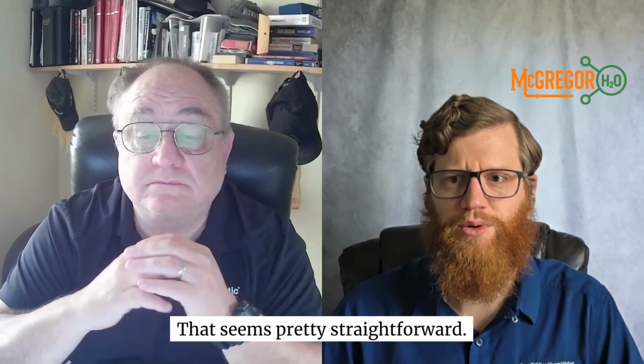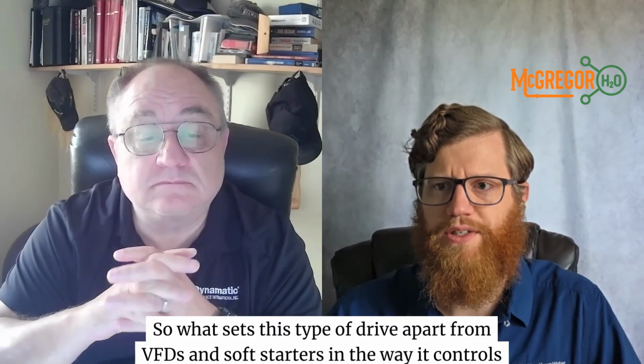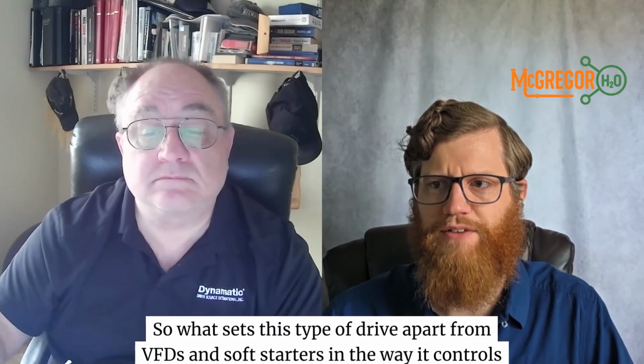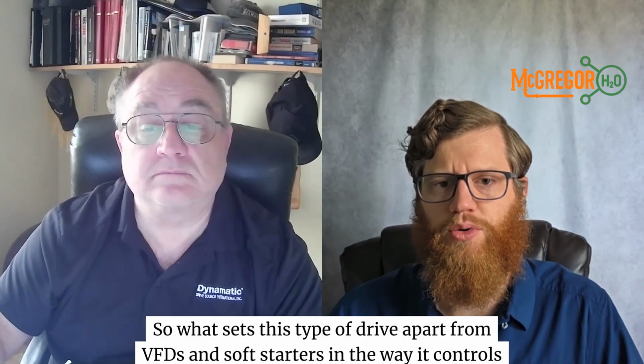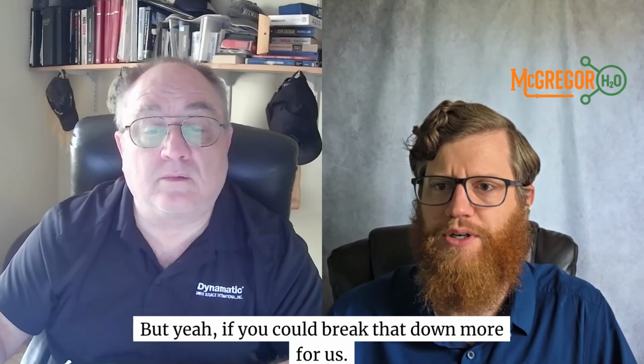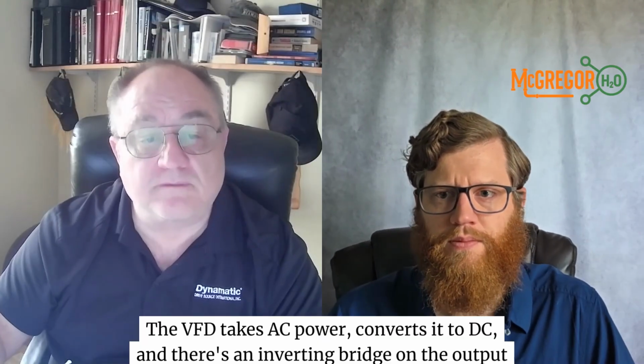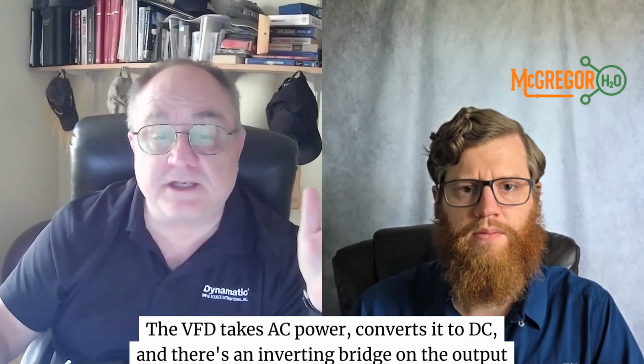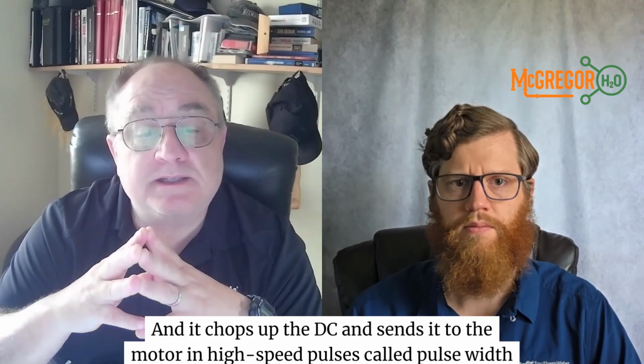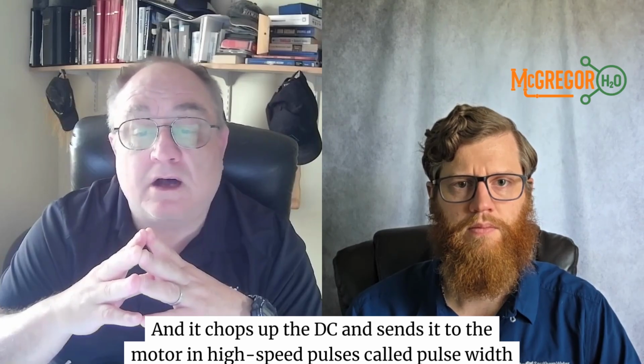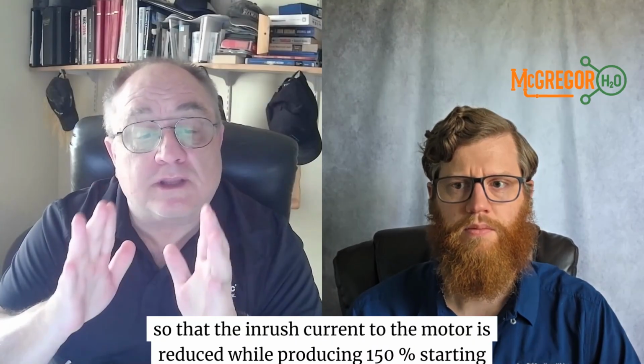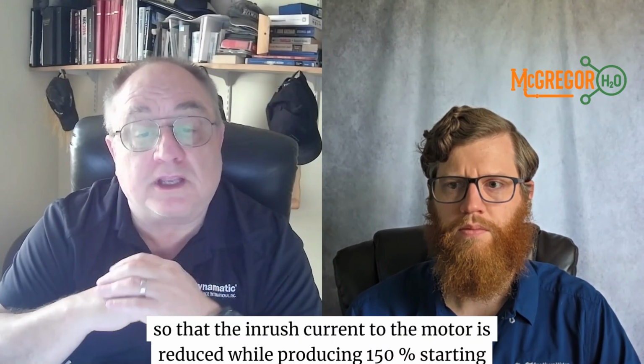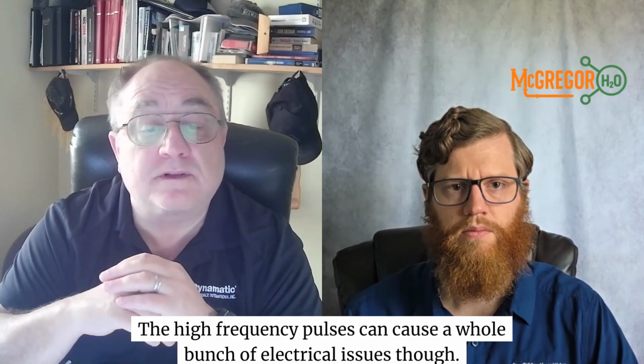That seems pretty straightforward. So what sets this type of drive apart from VFDs and soft starters in the way it controls speed? I guess you kind of touched on that in the last question, but if you could break that down more for us. Sure. The VFD takes AC power, converts it to DC, and there's an inverting bridge on the output stage of the VFD, and it chops up the DC and sends it to the motor in high-speed pulses called pulse width modulation, or PWM for short. PWM is regulated so that the inrush current to the motor is reduced while producing 150% starting torque. The high-frequency pulses can cause a whole bunch of electrical issues, though.